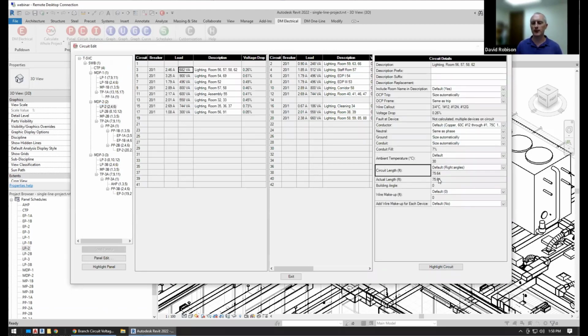So if I do default, on average, those light fixtures are 75 feet away from the panel. And then for our voltage drop calculation, we put the entire load at that average distance and calculate the voltage drop based upon that. And then for fault, we will just use the wire length and the wire size to calculate the fault. So that's partly why we don't do fault to multiple devices, because it kind of all falls apart. But if there's one device, it works, and so we can calculate the fault.